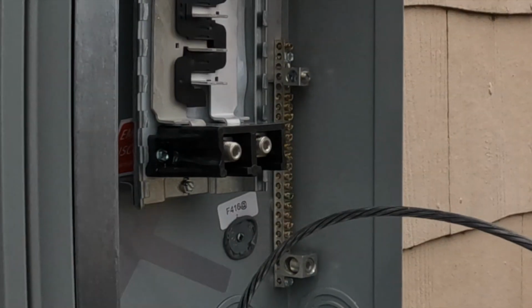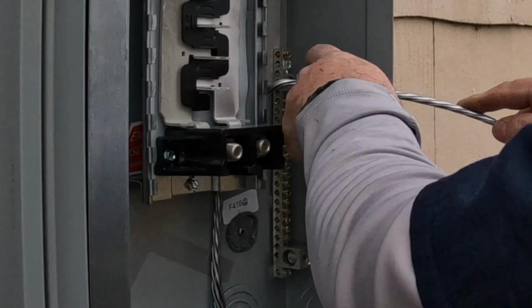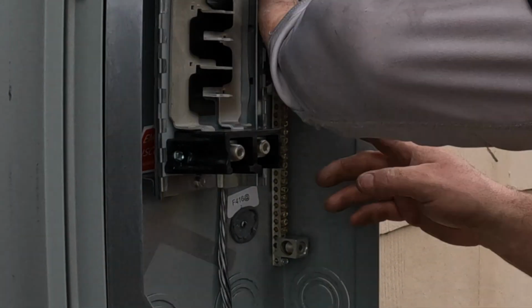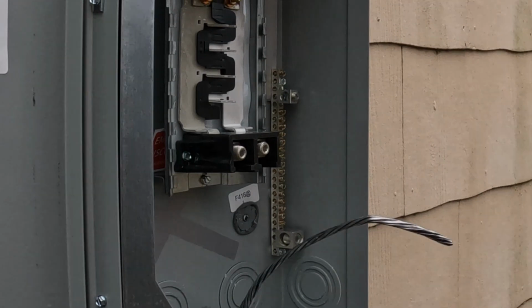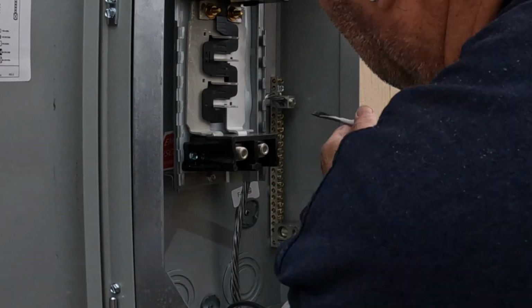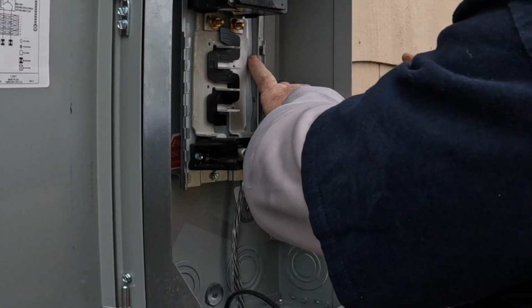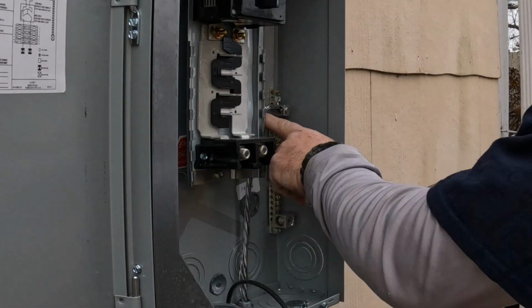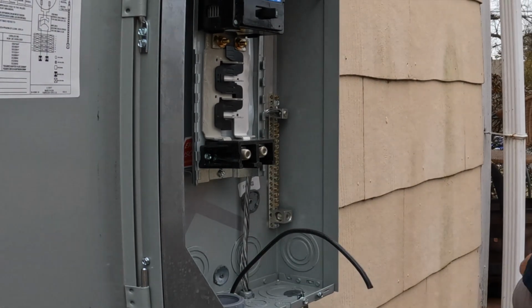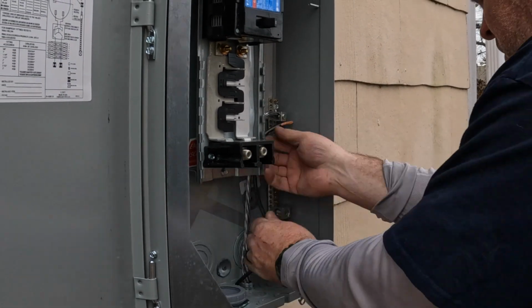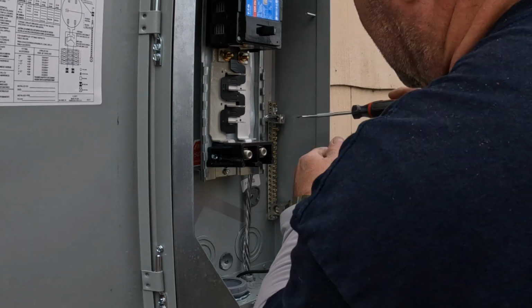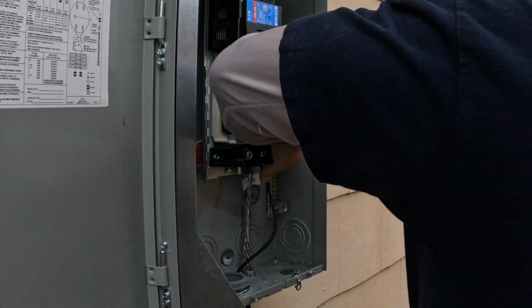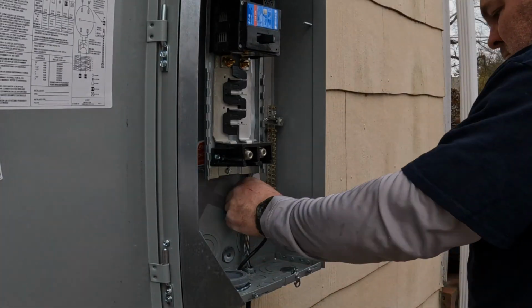This is my primary grounding electrode conductor. This is number 2 aluminum that I'm terminating. All of my grounding electrode conductors and my system neutrals get bonded here at the main disconnect. That's my grounding electrode conductor that goes to my 2 copper ground rods in the ground, and this also gets terminated here at the main disconnect. The main disconnect is where all of your grounding and bonding takes place.